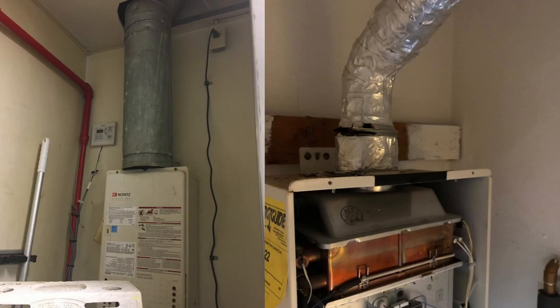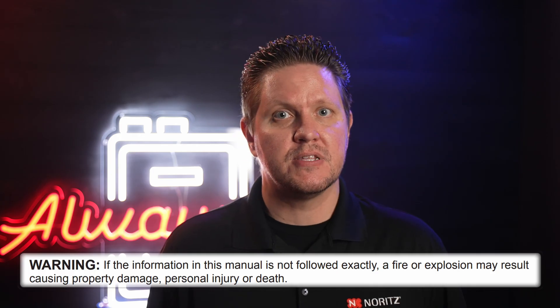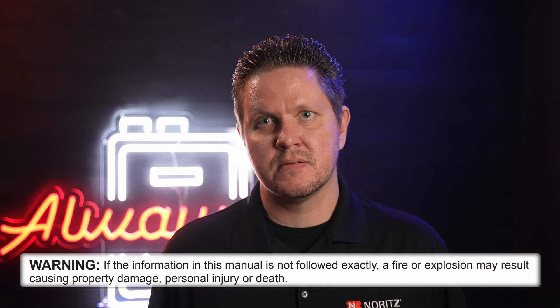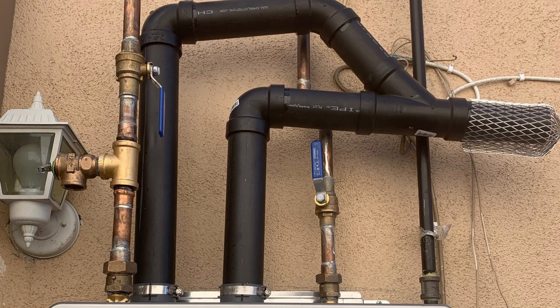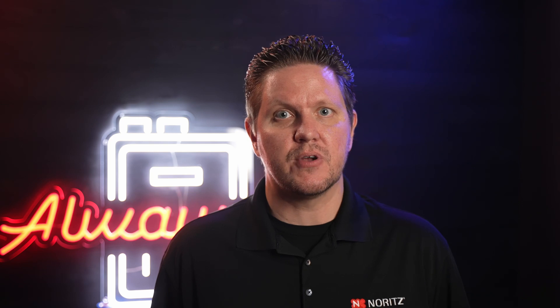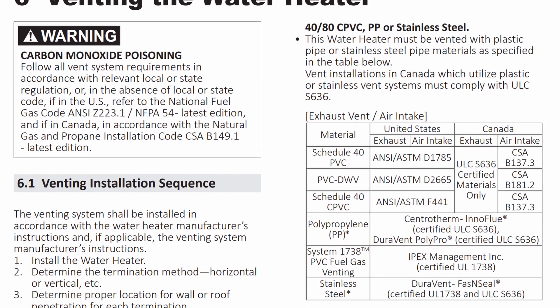Poorly or incorrectly installed venting can not only cause problems with the unit's operation, it can put the occupants of the home at risk in extreme cases. In less extreme cases, bad venting or terminations can cause the unit to draw in its own exhaust, snuffing out the flame. Terminations without the proper clearance, incorrectly assembled concentric terminations, or using standard end vent on a unit that requires specialized concentric venting can all cause code 12s, noises, or other combustion issues. It's imperative that the guidelines in the installation manual are followed, otherwise you're just asking for problems.